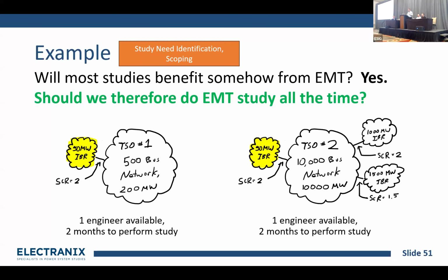So we've got two systems here. The first system on the left is TSO number 1. They've got a 500 bus network with a peak load of 200 megawatts, and they're connecting a 50 megawatt IBR. The short circuit ratio at the point of interconnection for the IBR is 2. So we're going to say that meets our criteria — we should do a study.